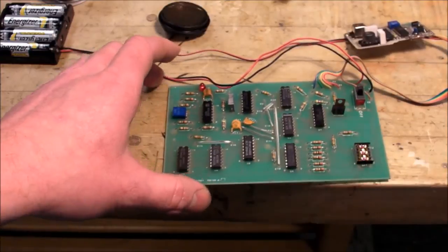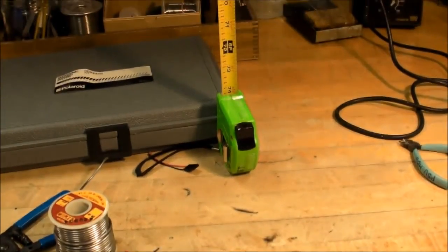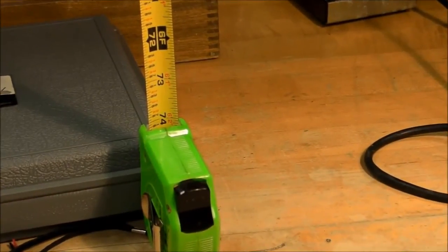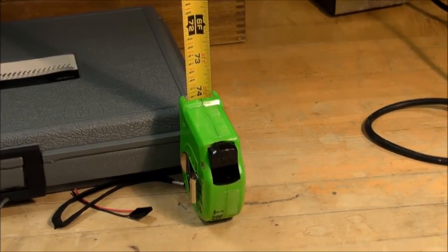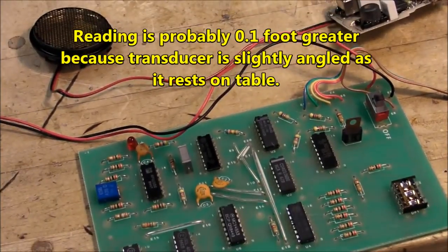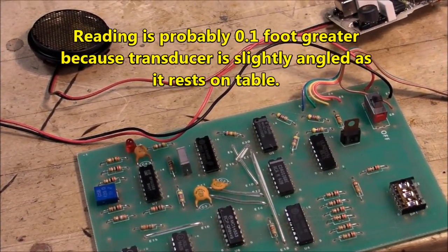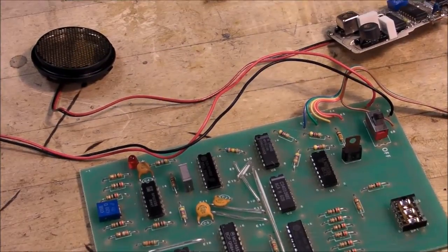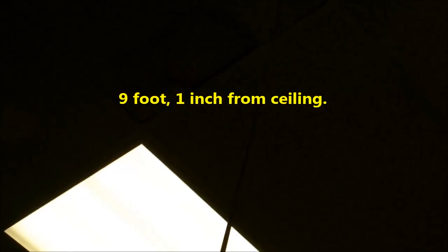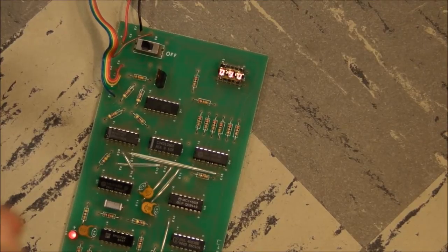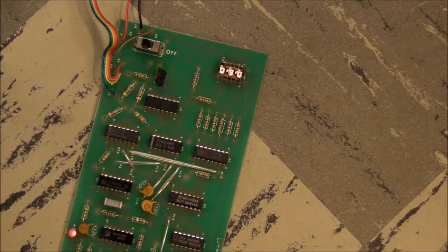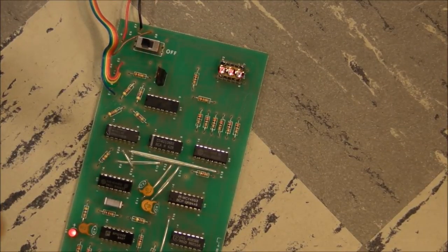I should measure that to verify. And all the way down to the table, look at that. It's probably closer to 6.4 feet to the table, and this thing was giving me a 6.5, but that's fine because according to the specs, it's good to plus or minus 1/10 of a foot. Let's try measuring it from the floor. It's going between 9.0 and 9.1, so that's pretty good. Not bad for 28-year-old technology that's never been used before.